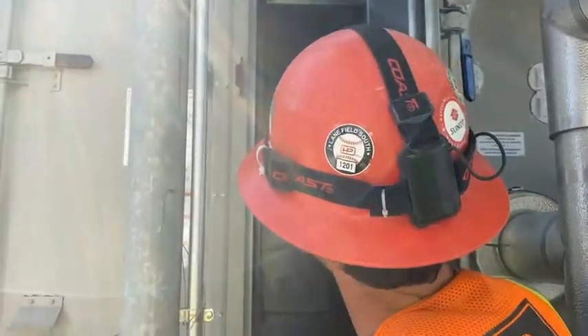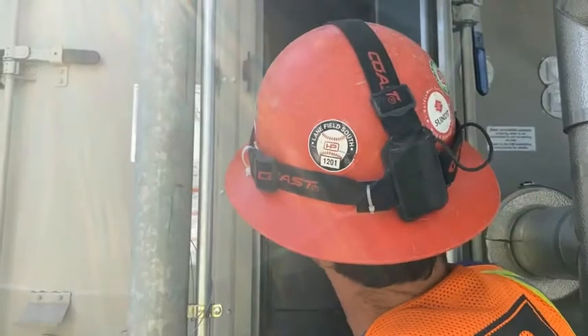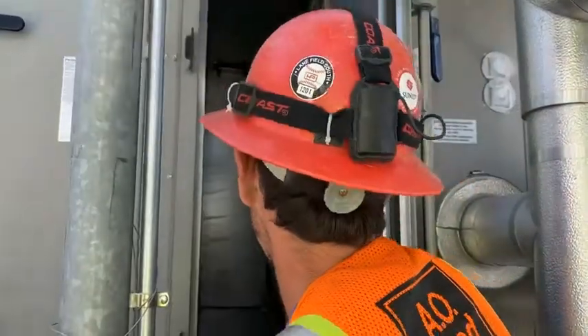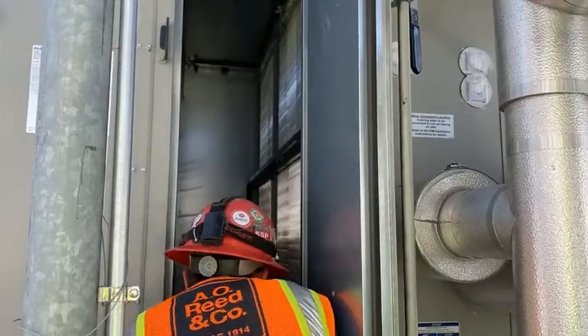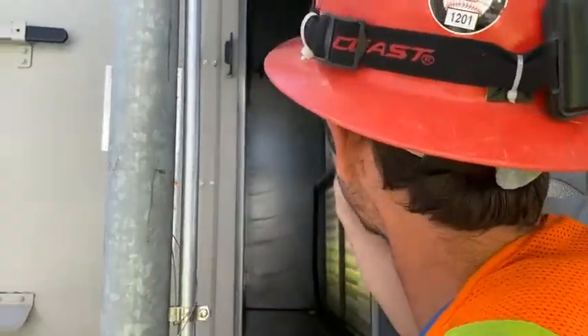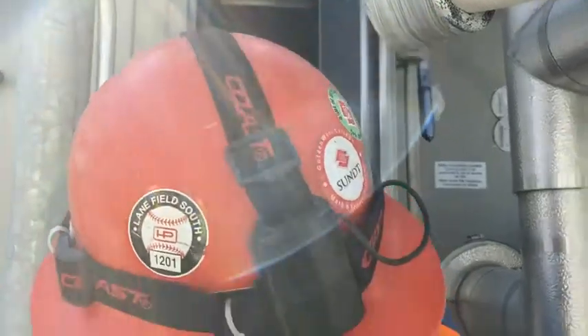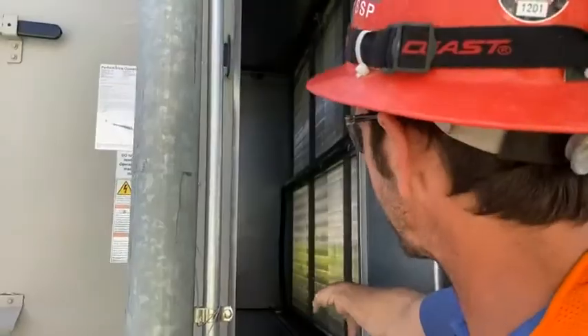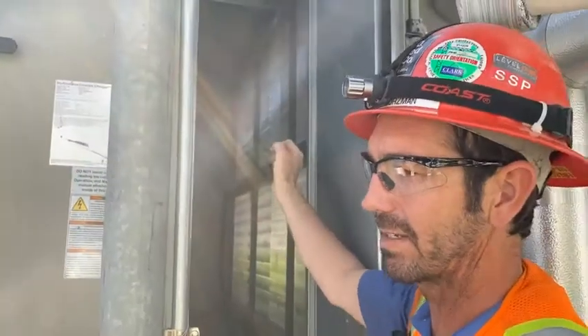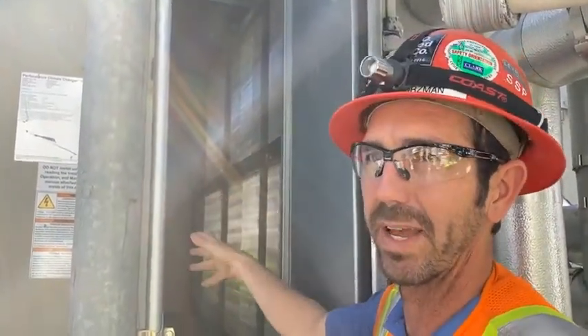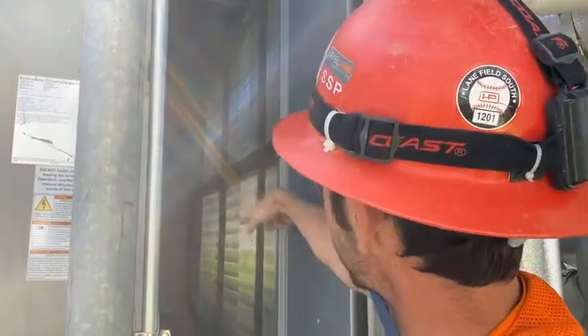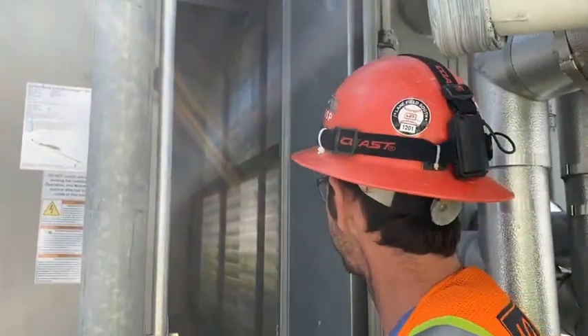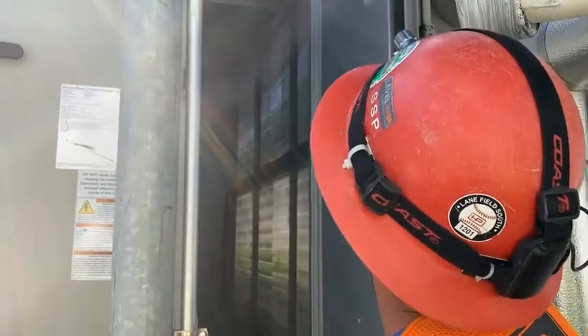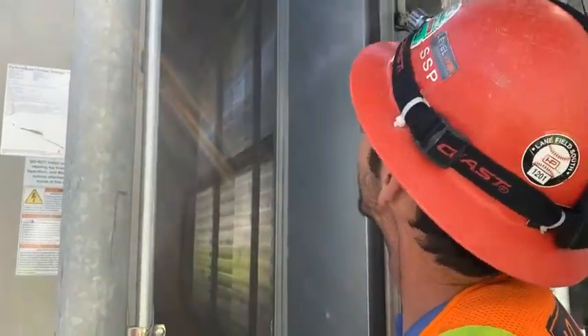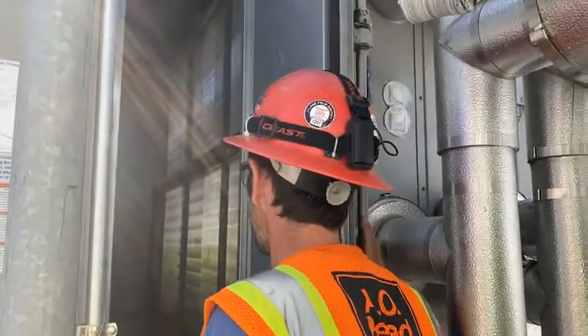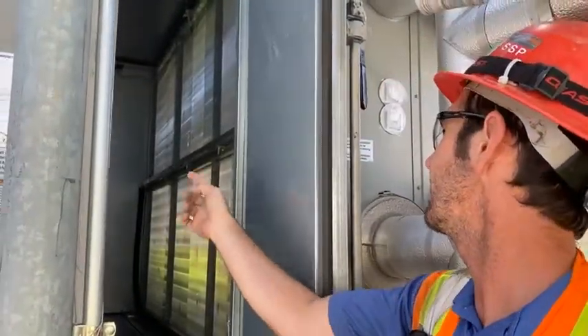So this will be how you get to your cooling coil, the drain pan. There's an upper drain pan that drains down into the lower drain pan. There's 2 drain outlets on either side of the air handler that will funnel the upper drain pan down to the bottom drain pan. Make sure the hoses stay on the unit. If they don't, as the water can drip down, it can get sprayed outside of the drain pan and cause a mess. Okay? So we want those drain hoses to remain on the upper pan to the lower pan. Questions on this compartment?